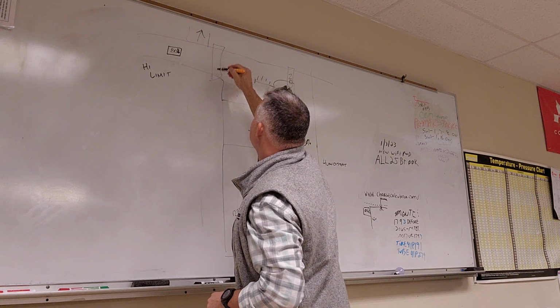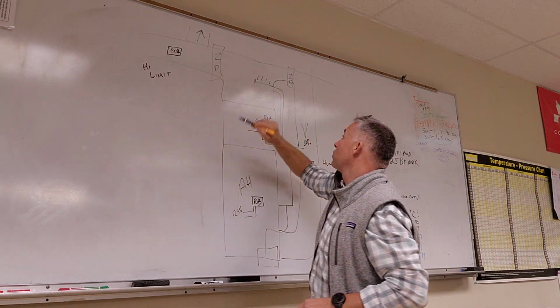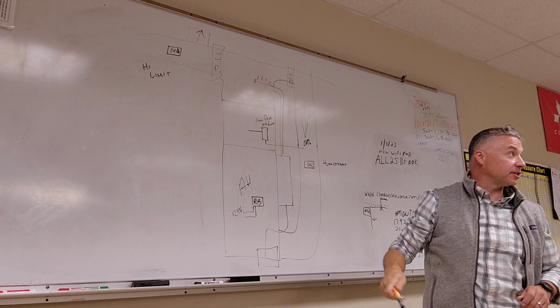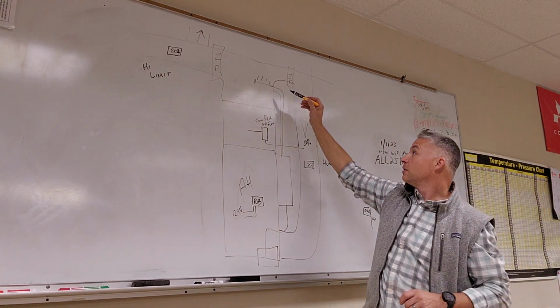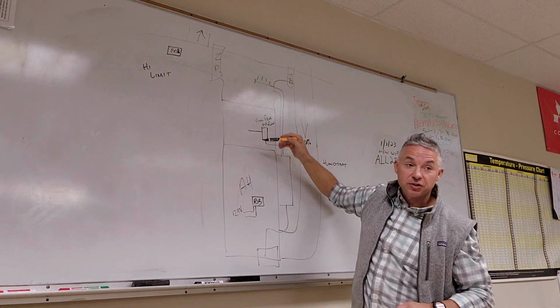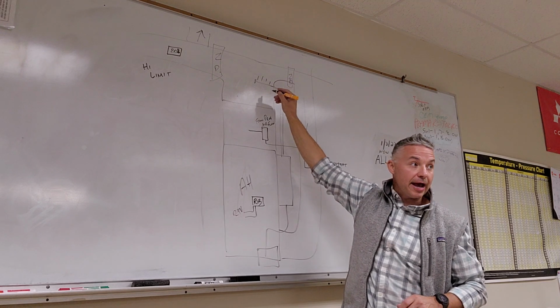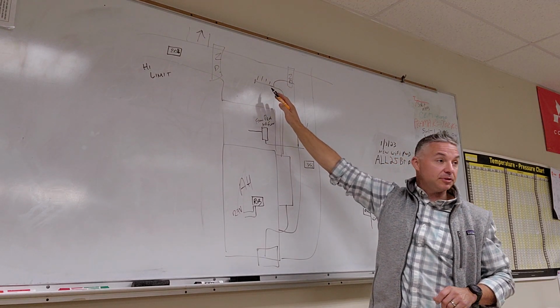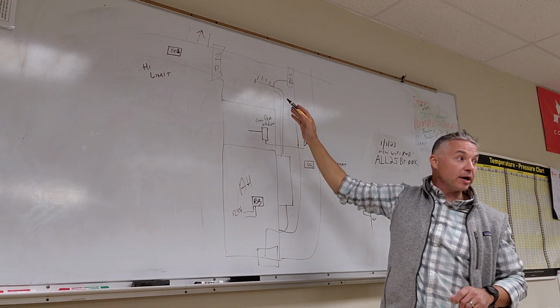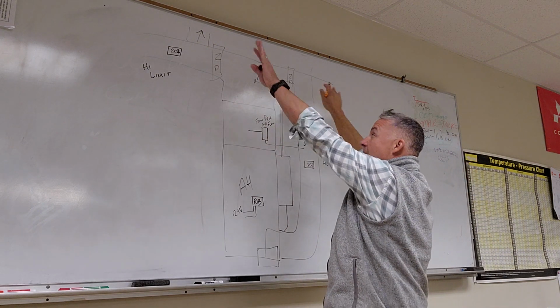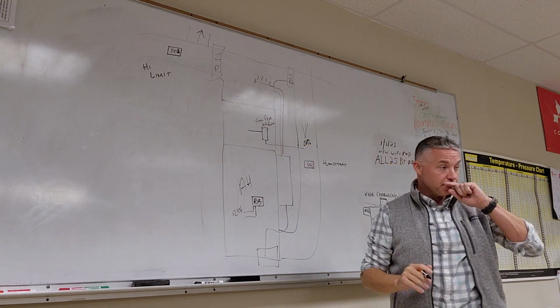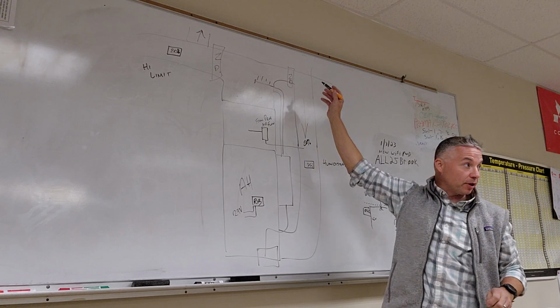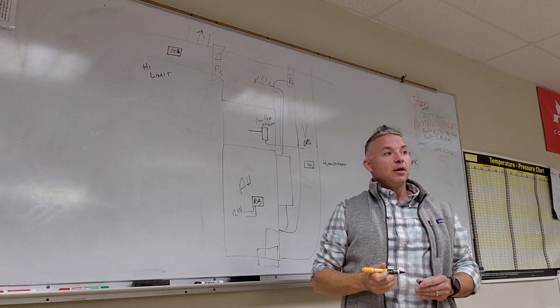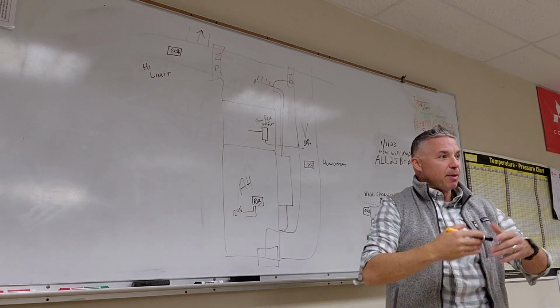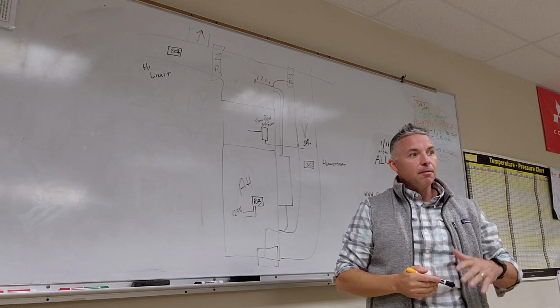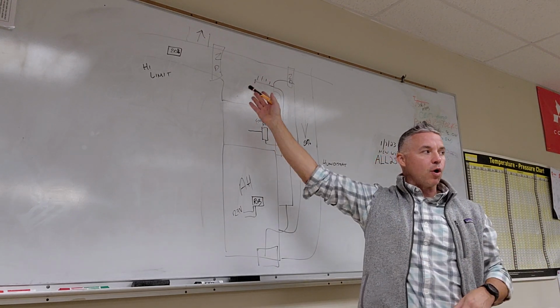You're running two high limits, right? Or no? Often we're going to run two high limits, because if we're doing multiple trunk lines, we may not have all the space that we need to install that steam distributor, because we want to install it in such a way that any zone will get the humidity. You don't want to put it downstream in only one of the zones. We do want all the zones to get it if possible, but it's not going to kill you if you only put it in one of the trunk lines.